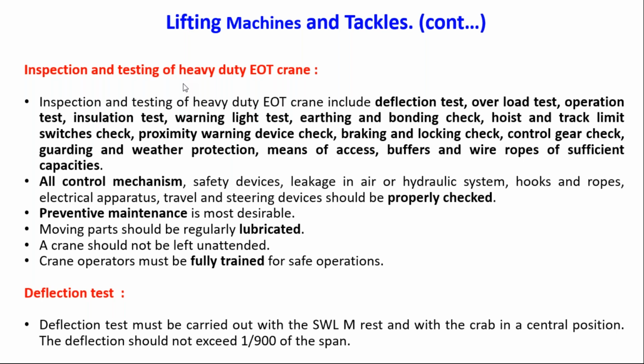Other than this, inspection and testing of heavy duty EOT cranes include the deflection test, overload test, operation test, insulation test, warning light test, earthing and bonding check, hoist and track limit switches check, proximity warning device check, braking and locking check, control gear check, guarding and weather protection, means of access, buffers, and wire ropes of sufficient capacity. These are the different parameters we have to check every year for these EOTs.